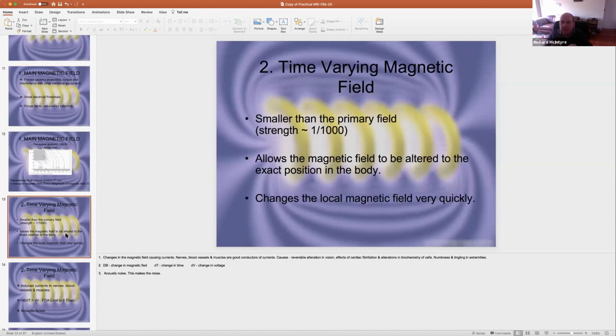The time-varying magnetic field alters the magnetic field inside the magnet very, very quickly. Okay, and the gradients I mentioned earlier, the gradients do that. So the gradients change the magnetic field, and it superimposes a new magnetic field onto the existing magnetic field. So when I say that, I mean you've got a bore of the magnet, and you know that that's 3 Tesla at the isocenter. Okay, and where we're scanning is completely homogeneous. It's going to be 3 Tesla. The gradients superimpose a magnetic field over that.